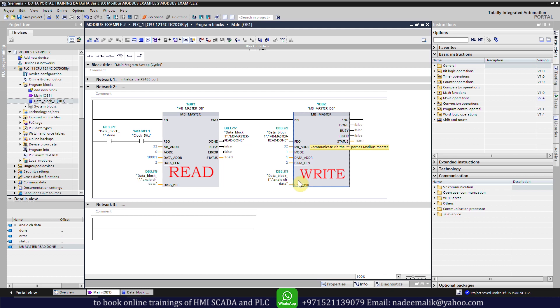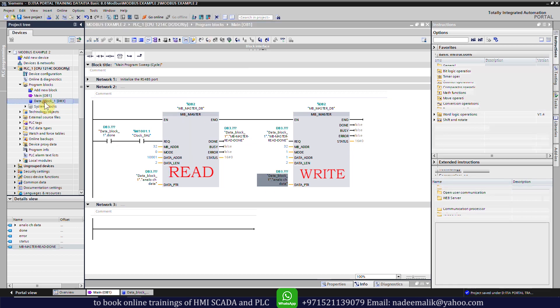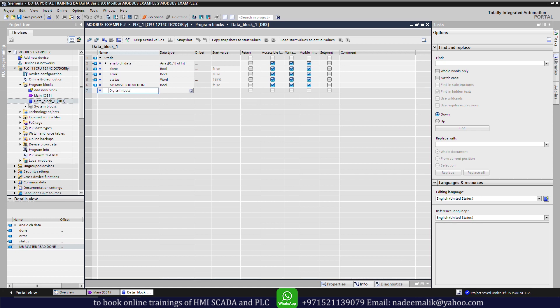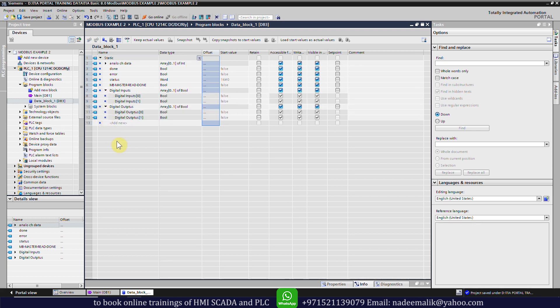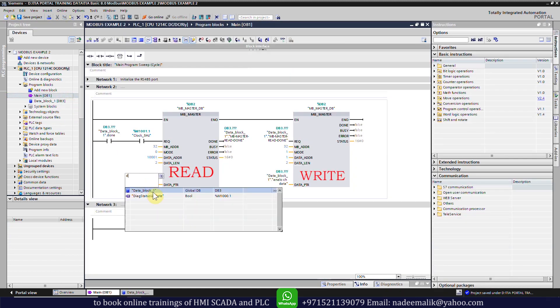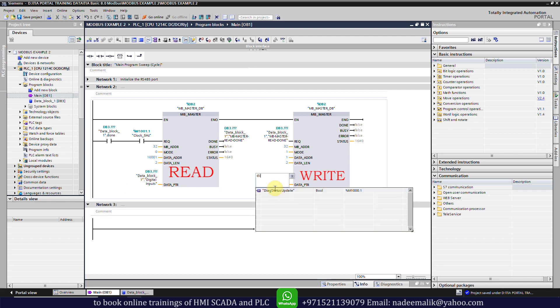Next we need to assign data tags to the data pointers of both the read and write functions. We will open data block DB3 and create a digital input tag as an array of 2 with boolean data type. We have created two input data tags to show the status of the two selector switches, and two output tags to turn on or off the digital outputs of the extension IO card. We will then select the digital input array tag in DB3 for the data pointer of the read function, and the digital output array tag for the pointer of the write function.